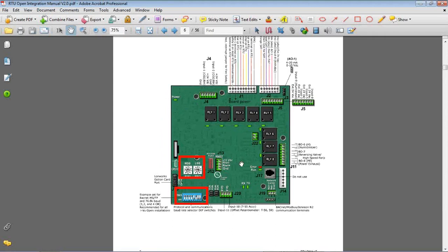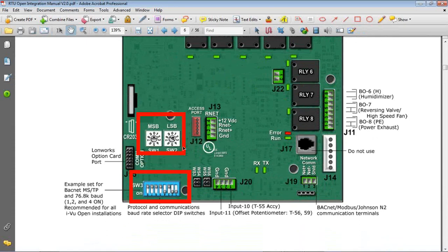And both of those configurations are actually hard set on our controllers. If you look at these two red boxes here, we have two rotary switches for setting the address of our controller. So if you wanted to address it as 99, you would set the tens digit to 9 and the ones digit to 9. Each controller on the communication bus can go up to 99 addresses.